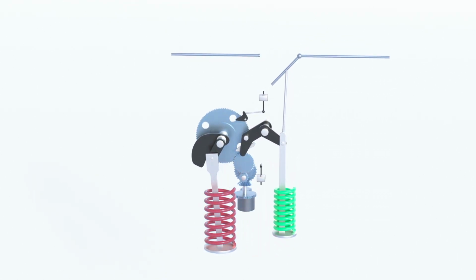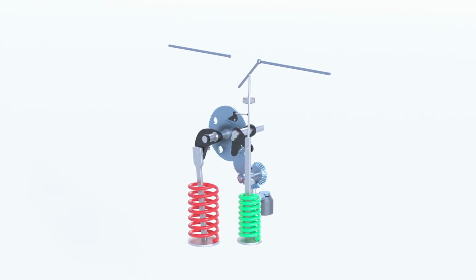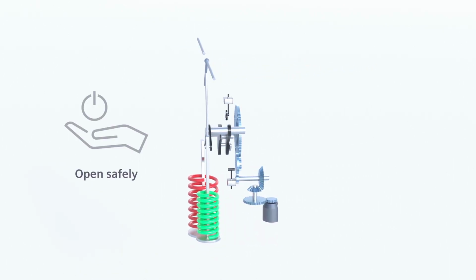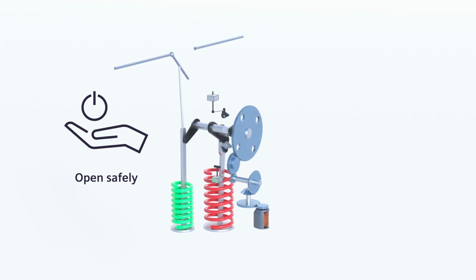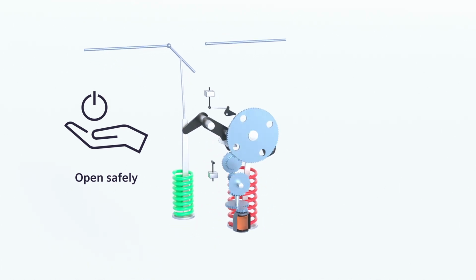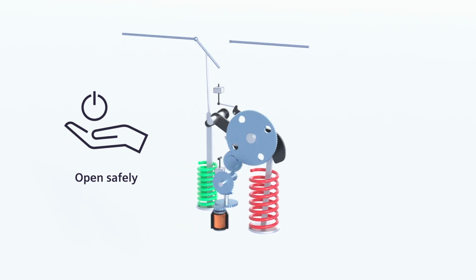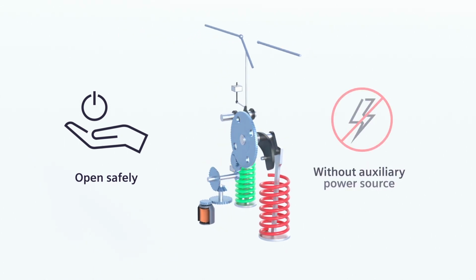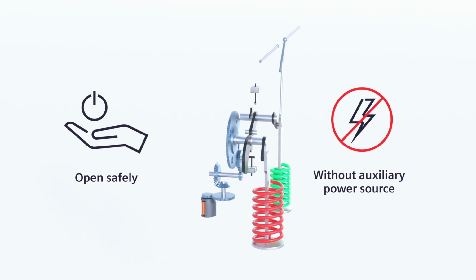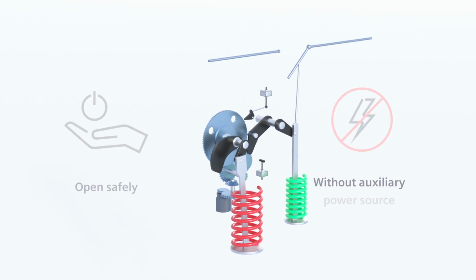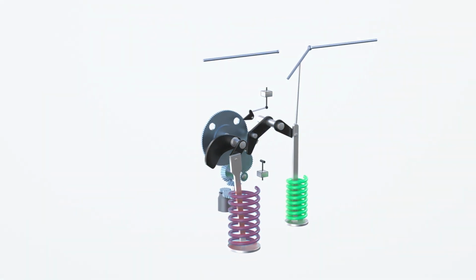The opening spring is generally charged through the closing spring. Therefore, the circuit breaker can be opened safely and immediately at any time. In normal operation mode, the circuit breaker is able to perform open, close, open operation sequences without any auxiliary power source for charging the springs.